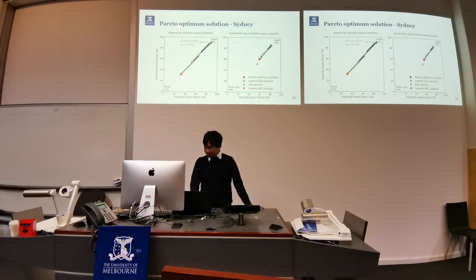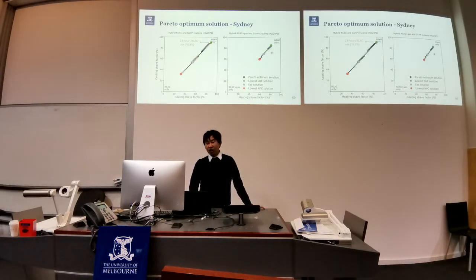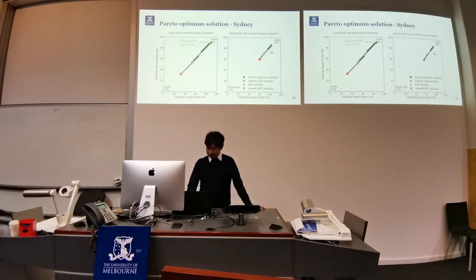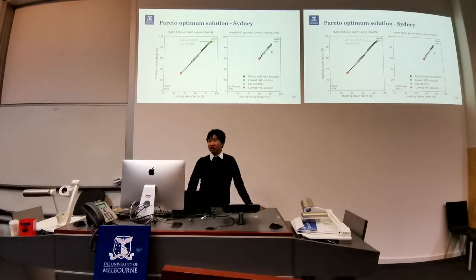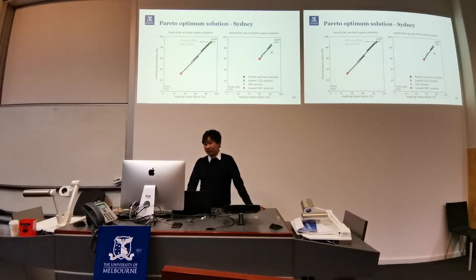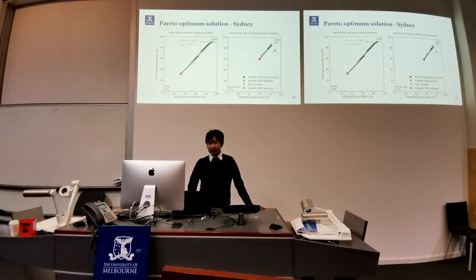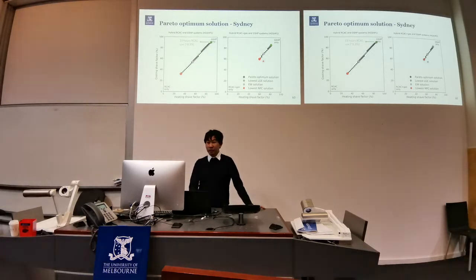For hybrid system 2, you can see here that the Pareto optimum solution range is much shorter. This is because the ground source heat pump system is significantly more efficient than the gas system. So the lowest cost solution is significantly closer towards the right-hand corner, where the ground source heat pump system would be preferred.